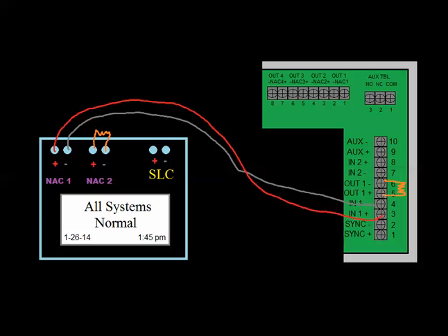But it needs a reverse polarity input. So right now, as we've already learned about NACs, this positive and negative are actually reversed in a standby state on this panel. When this panel goes into alarm and this NAC turns on, the polarity is going to reverse, and it's going to generally increase depending on your panel. And now you'll have 24 volts positive going onto this terminal, which is going to put this into alarm and turn on all of the NAC outputs.